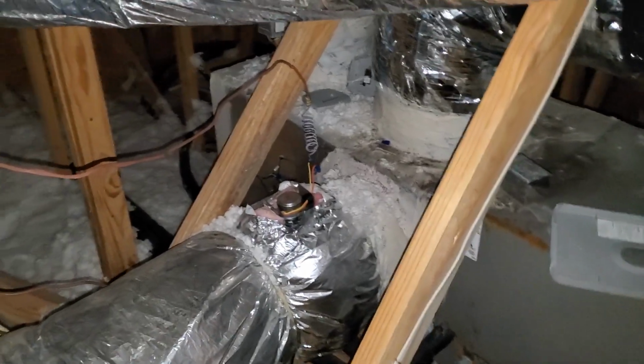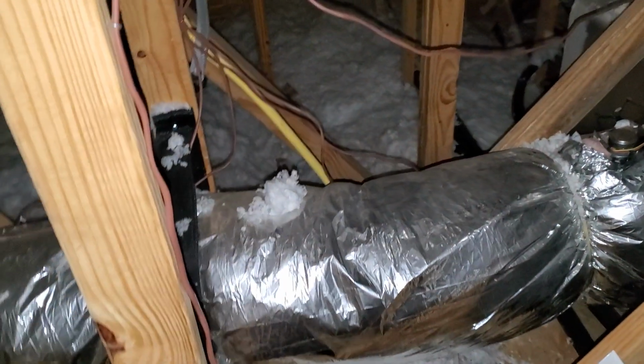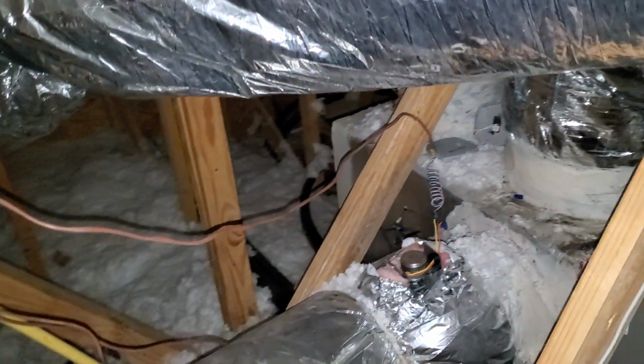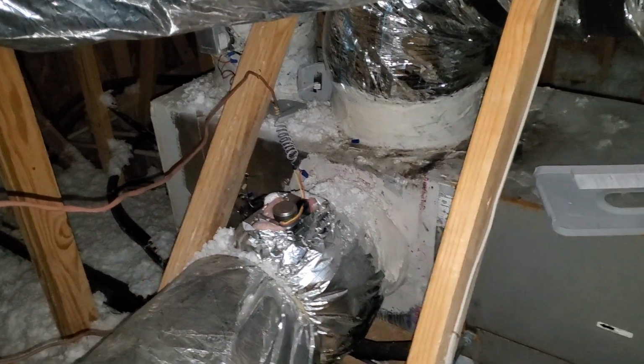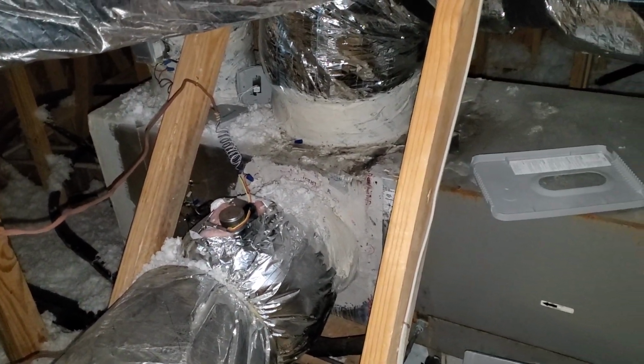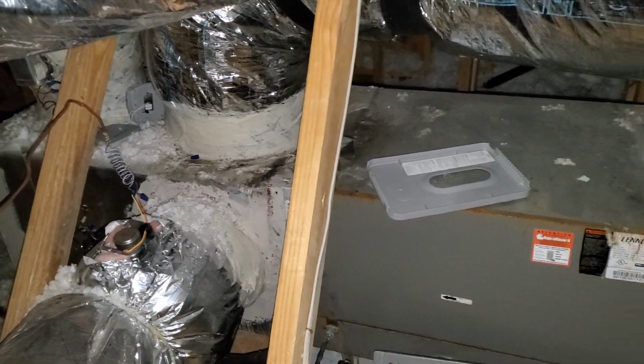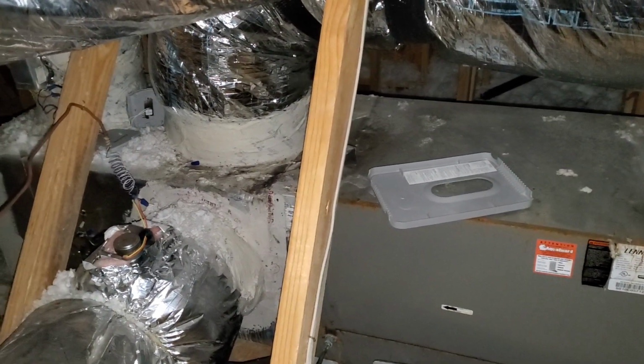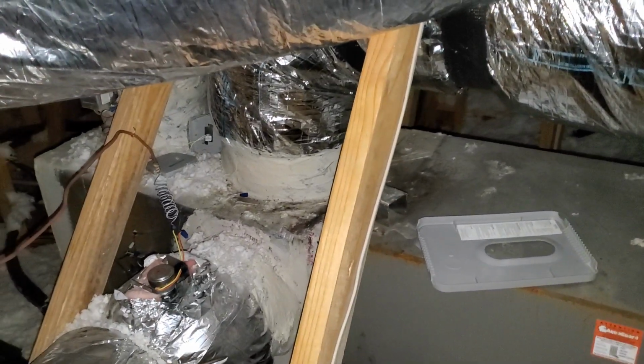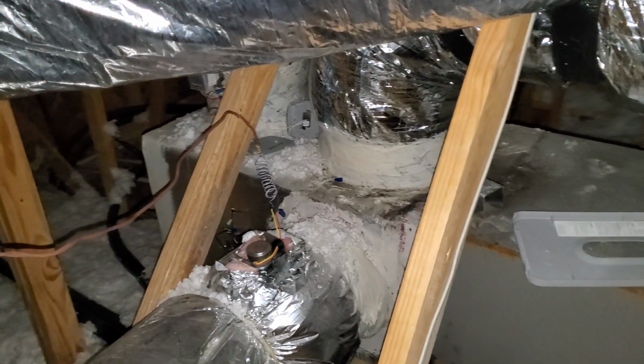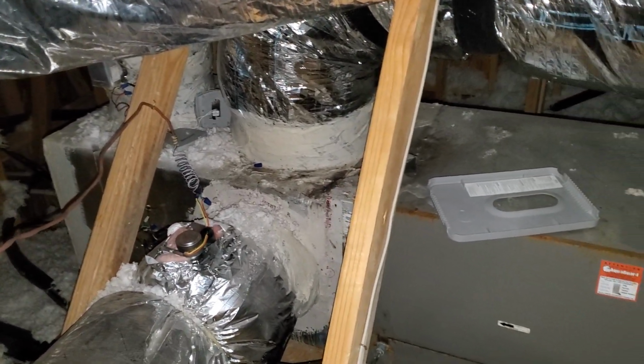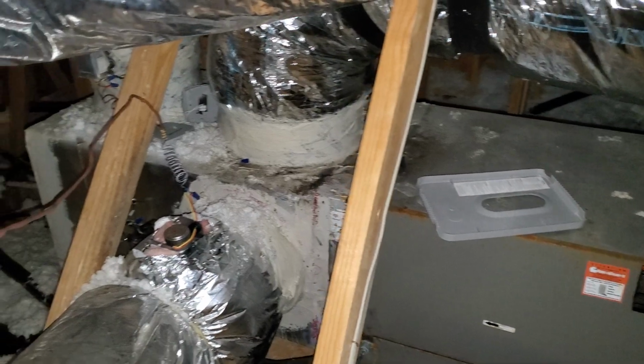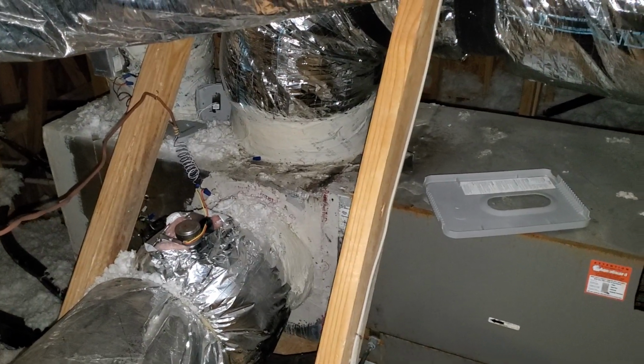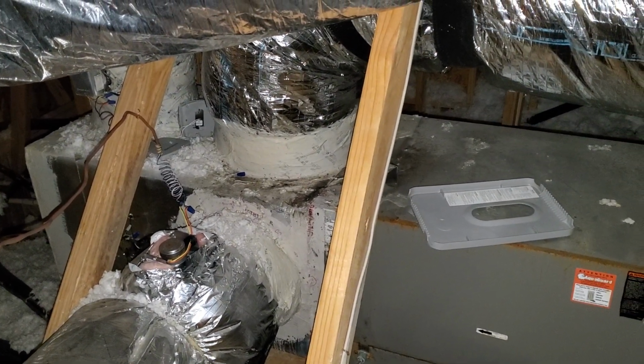What's going on, guys? Out here on a no heat call. This house has two gas furnaces, two Lennox gas furnaces, and I'm just going to show you what I found. Another technician was out here, condemned the furnace control board, said it wasn't sending power to the gas valve, and the discharge air sensor was bad. So I came out here for the first time, changed the board, changed the DAT sensor, and just started turning everything on and looking around.